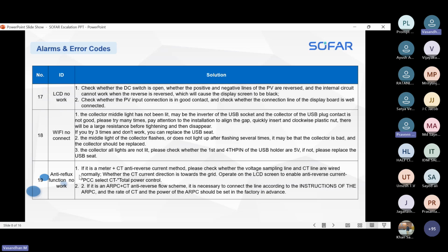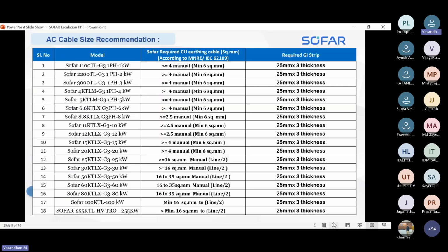If the anti-reflux function is not working, that function is meant to prevent reverse current. If the CT line is not properly connected, we can also check that from our side, depending on the customer's requirement.